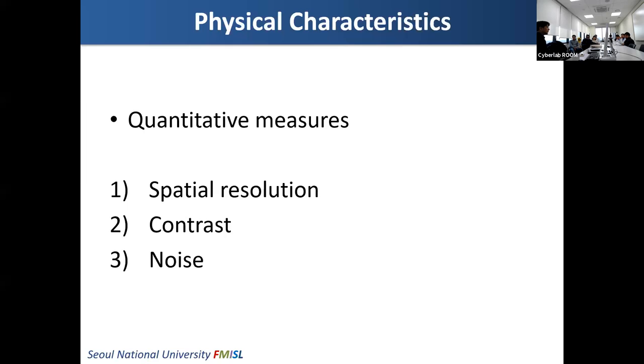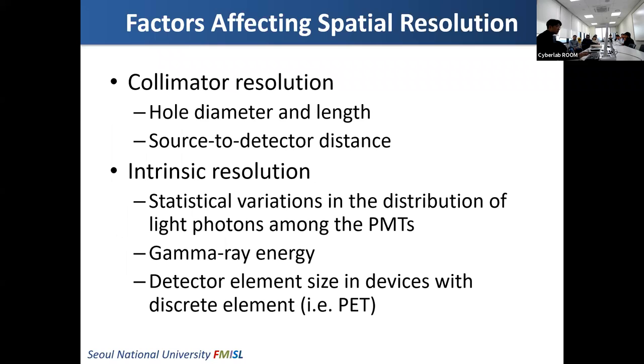Let's start with spatial resolution. What do you think affects the spatial resolution of nuclear medicine imaging systems? If we focus on the gamma camera or SPECT systems, the most important major component that determines spatial resolution is collimator resolution.